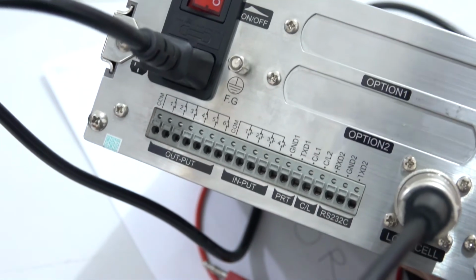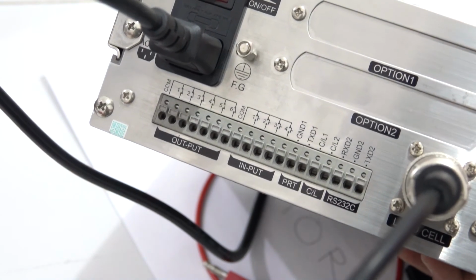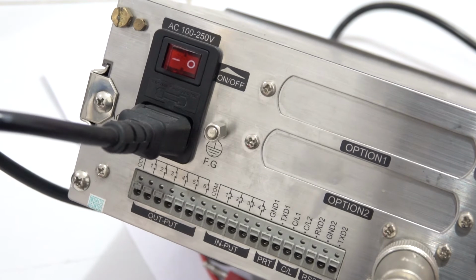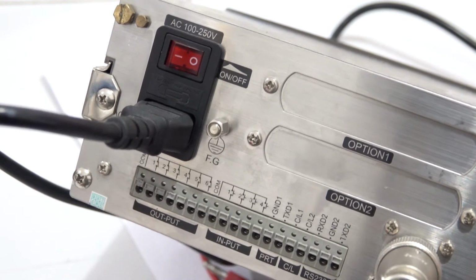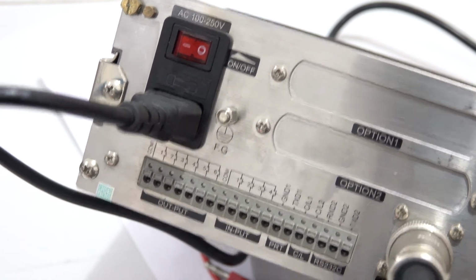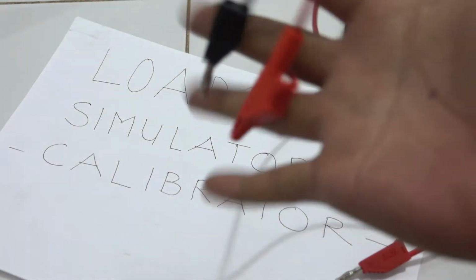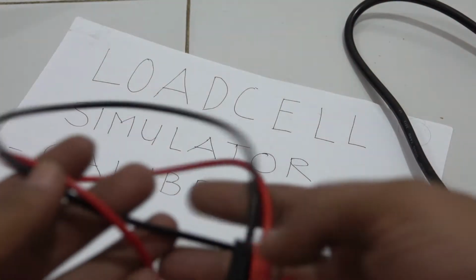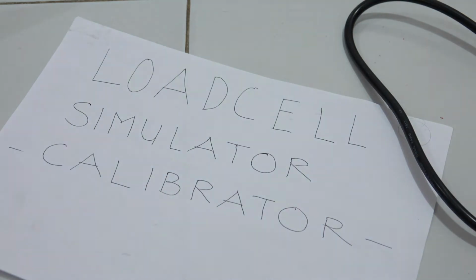And this one is the plug that connects from the junction box to here, and inside it there are converters from analog to digital and so on, and logic gates and so on, and the millivolt will be translated to the weight that you really need. Then you need some cables. These cables come together with this calibrator. And this is the calibrator box, the case. It's a very nice one.